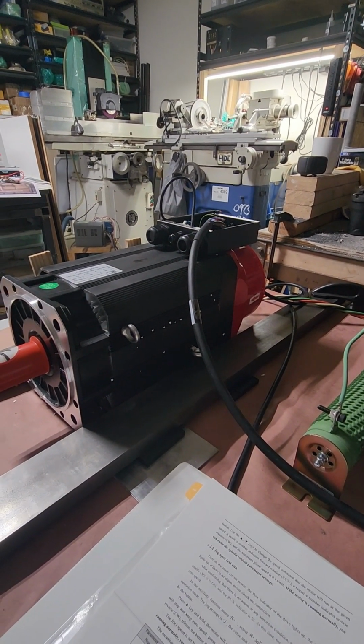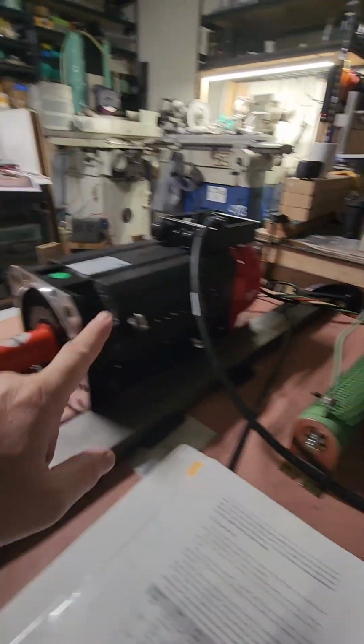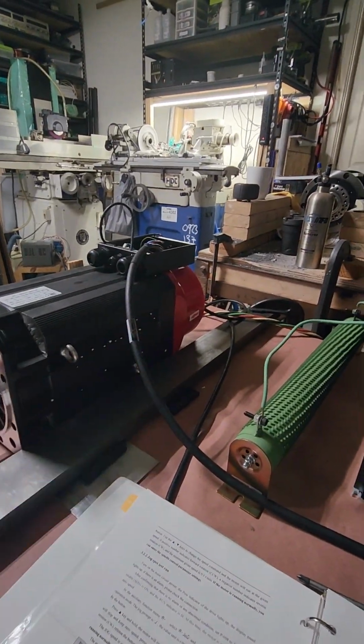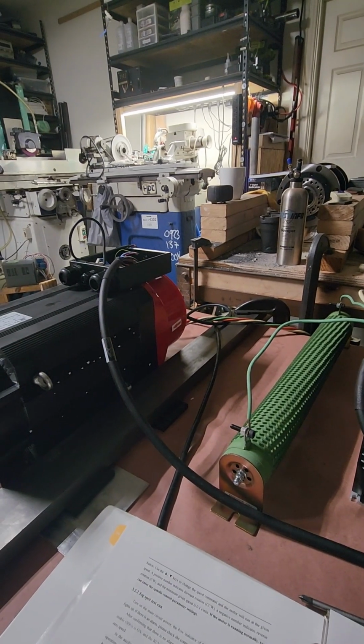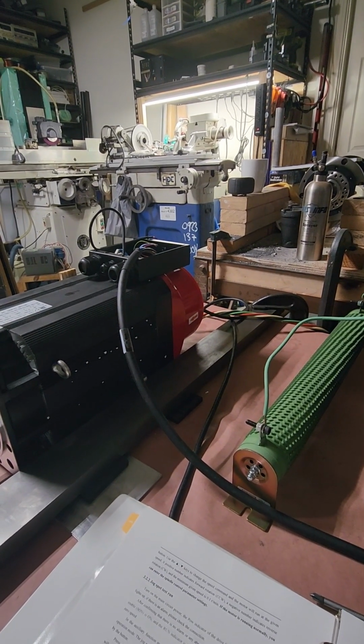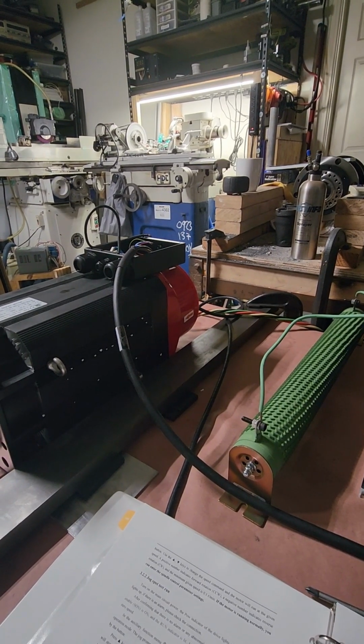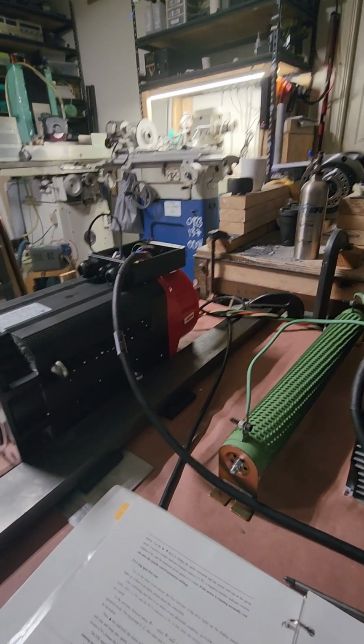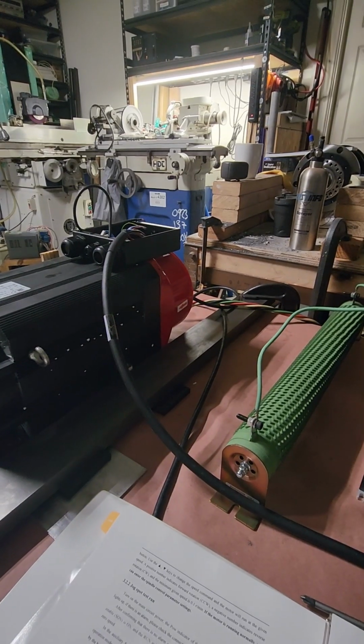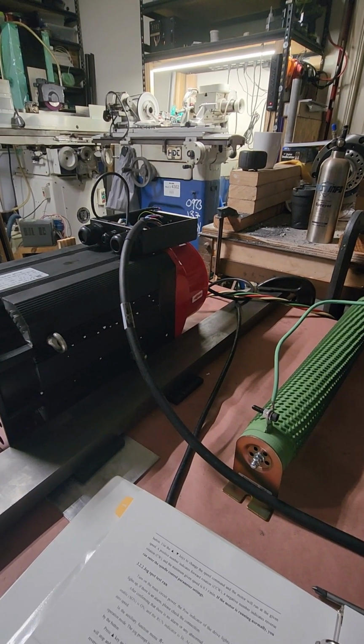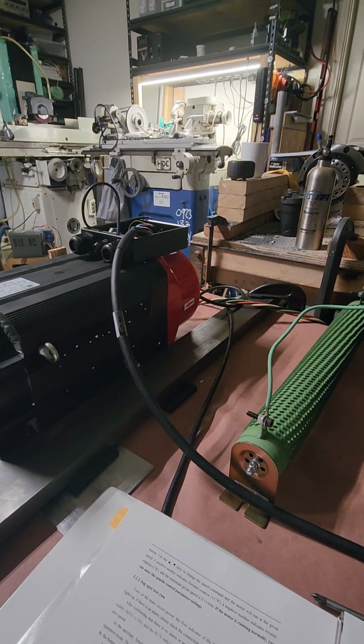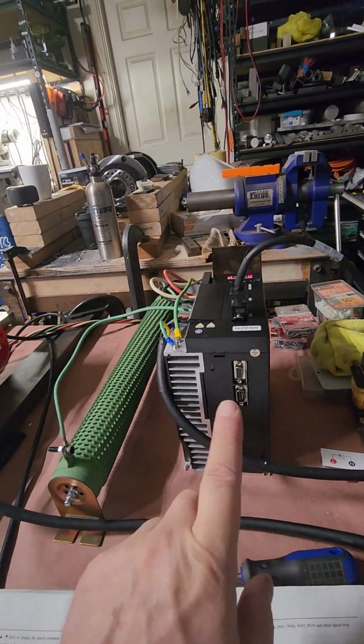The problem is if you run this at 3000 RPM, there are so many pulses per revolution per second that the drive can't handle it. So I need to put something in between to reduce that pulse rate by a well-known factor, like gearing. So the idea is, if you're running in speed mode, I'm running with that pulse rate reduced by a factor of 8, or whatever this drive supports.